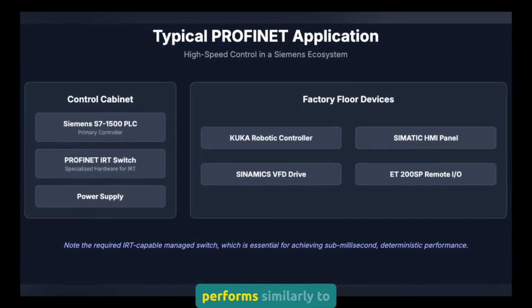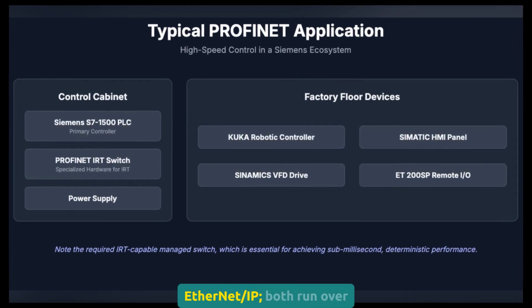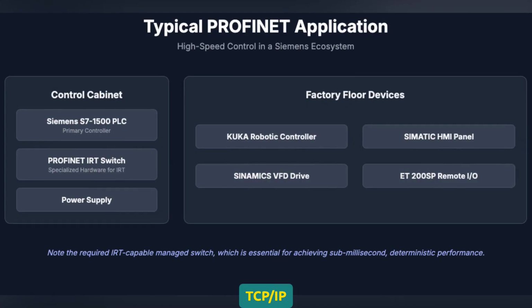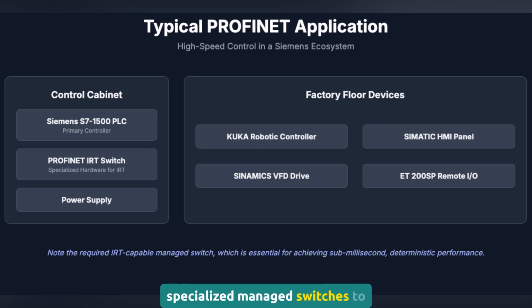PROFINET RT performs similarly to Ethernet IP. Both run over TCP IP infrastructure. PROFINET IRT is different. It uses specialized managed switches to achieve sub-millisecond performance. In Siemens heavy plants, it's a natural fit, but those IRT switches aren't cheap.